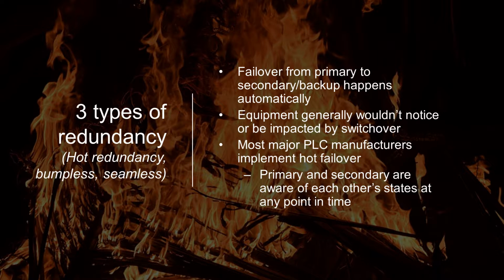Another word typically used for this type of redundancy is bumpless, because what's happening is you have a primary and a backup controller that are essentially in lockstep. They monitor the statuses of one another, and upon failure of one, the other automatically takes over.